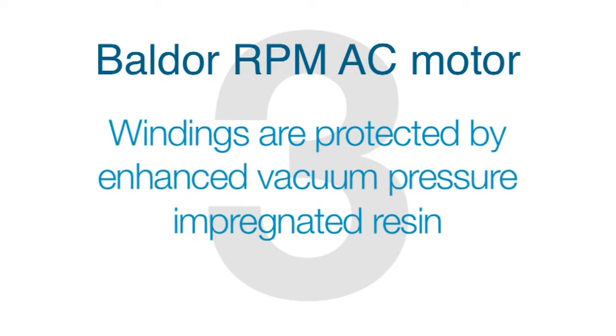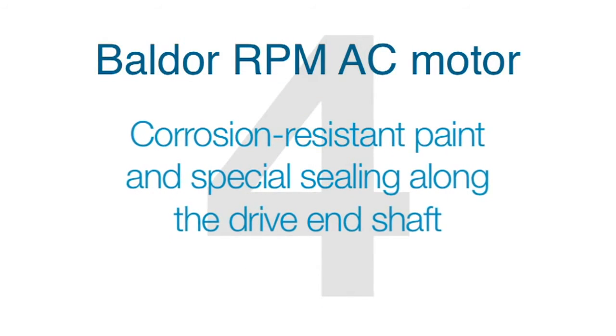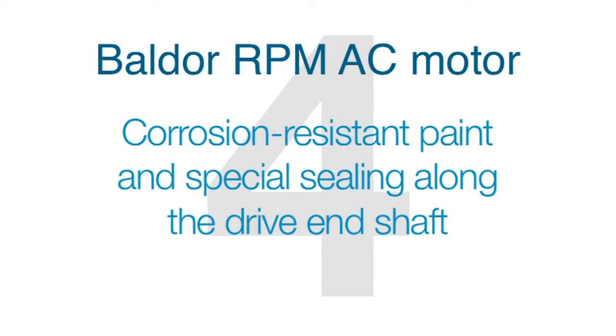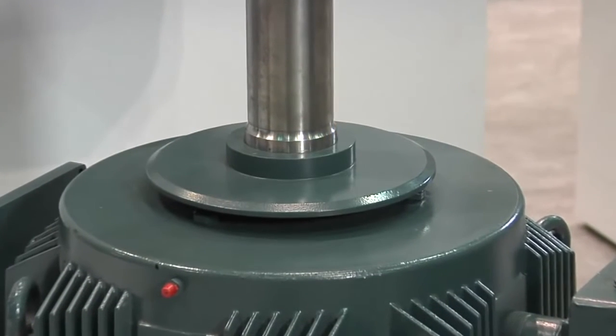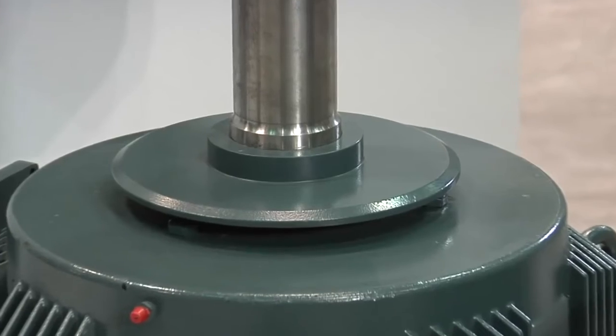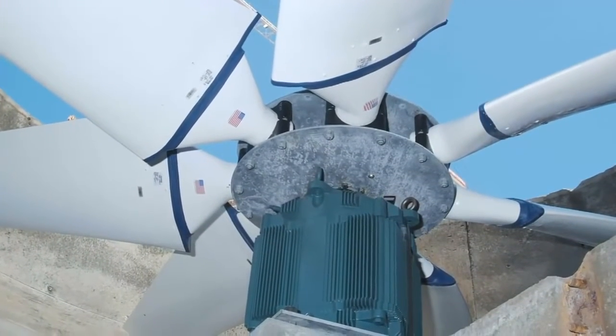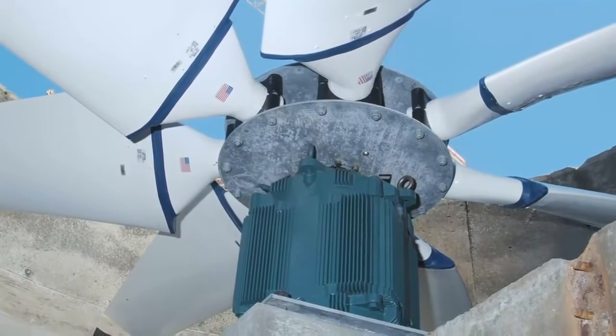Thirdly, the windings are protected by an enhanced vacuum pressure impregnated resin. This is the same type of treatment applied to motors used in offshore drill rigs and other severe applications. The resin completely penetrates the windings, filling the air voids and protecting the windings from damage even in wet, humid environments. And finally, the corrosion-resistant paint and special sealing along the drive end shaft enable the motor to tolerate the high humidity inside the tower. The motor is specifically designed to be placed directly in the cooling tower airstream.